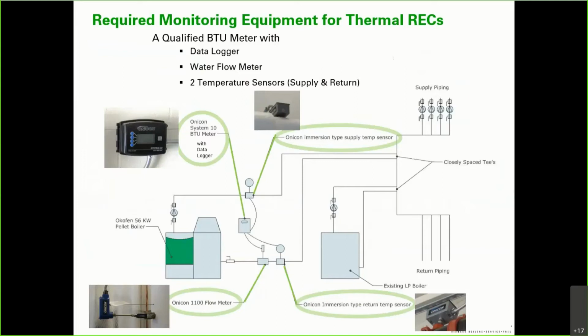Charlie talked about what it takes to put in a system. You need to invest in some BTU metering equipment. This just gives you an idea. It's maybe a little more complex than most people want to see, but this is the boiler here. On the piping, we have a monitor that looks at temperature in two different locations, both the supply and the return, or the output of the boiler and then what comes back from the building. We compare those two temperatures, and obviously the difference is how much heat the building used or how much we delivered to the building. And that's what we're counting.